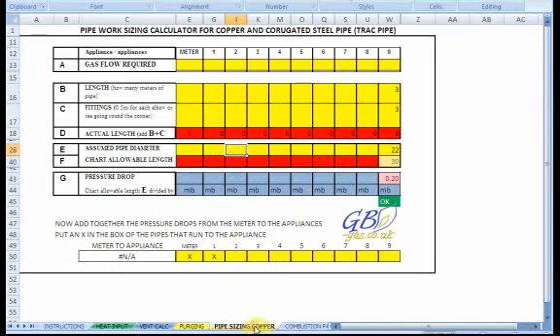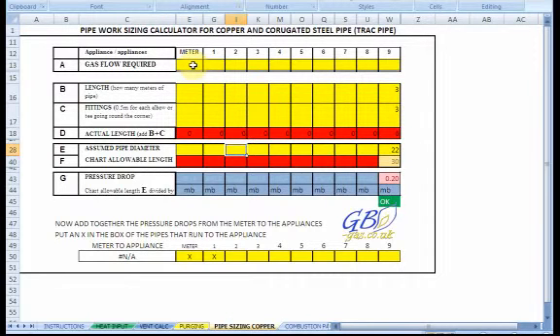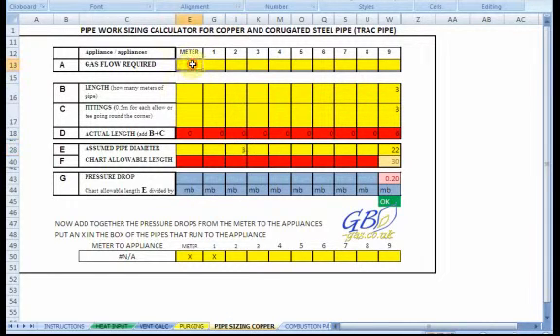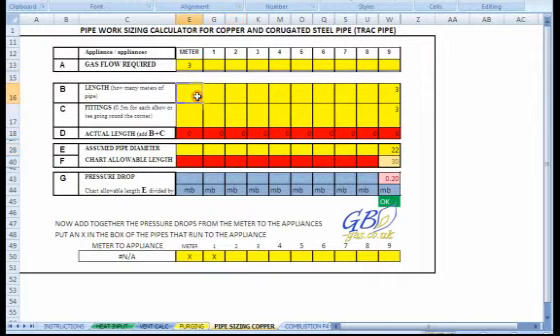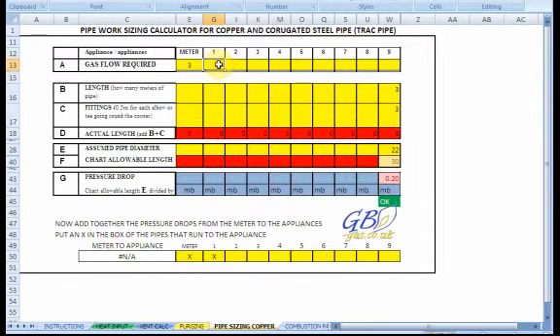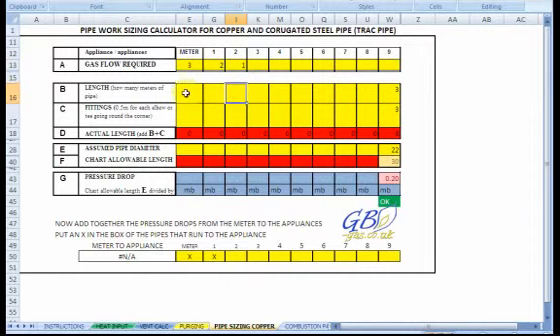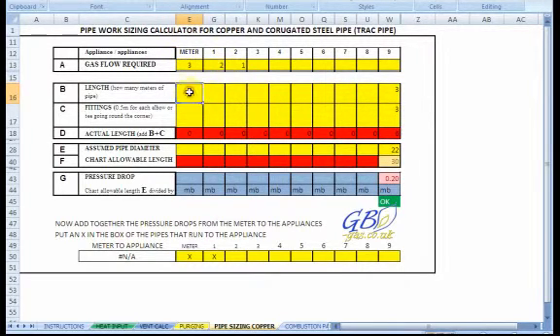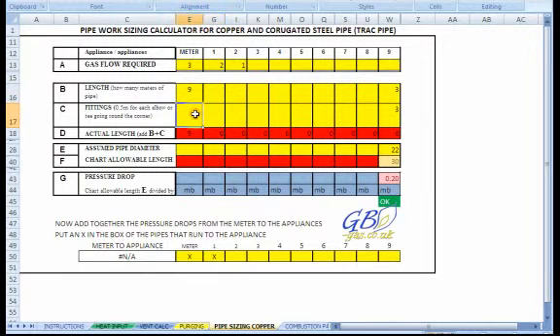For the pipe sizing in copper, we need to know the gas flow required in metres cubed per hour for each of the appliances. So, starting at the metre, if it's feeding two appliances, and we've got three metres cubed. And then the tee off splits down, and one appliance is two metres cubed, and the other appliance is one metre cubed. We can then put in the length of the pipe that we have, from this first point to the tee piece, where it splits to go to these two appliances. So, for argument to say, I've got nine metres of pipe, and I have got five elbows.